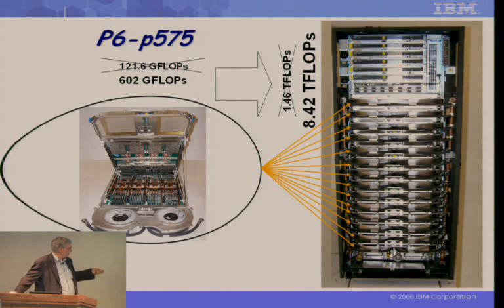It kind of has something like a car hood, if you will, so you can raise it up and look inside. Power supplies are in the top, DC to DC power supplies. Water cooling cold plates on the processors here, 16 processor modules. You see the DIMMs here. Blowers on the front take out the excess over and above what the water cooling handles, and you can see hoses come out at the front and tie into these manifolds.